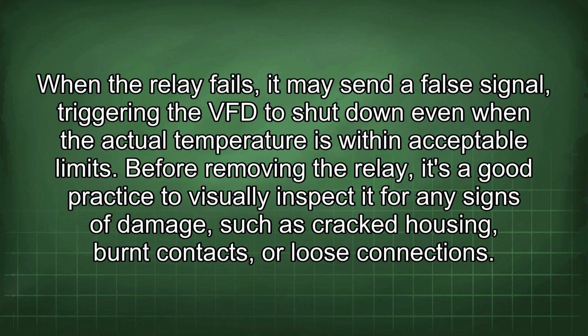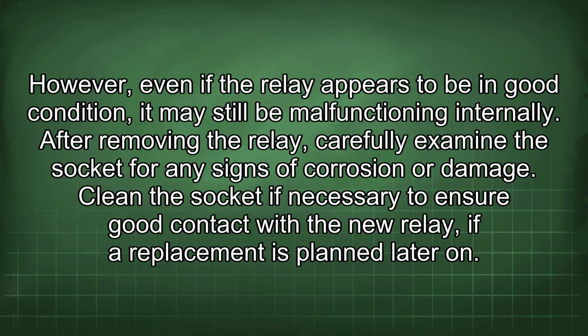Before removing the relay, it's a good practice to visually inspect it for any signs of damage, such as cracked housing, burnt contacts, or loose connections. However, even if the relay appears to be in good condition, it may still be malfunctioning internally. After removing the relay, carefully examine the socket for any signs of corrosion or damage. Clean the socket if necessary to ensure good contact with the new relay if a replacement is planned later on.